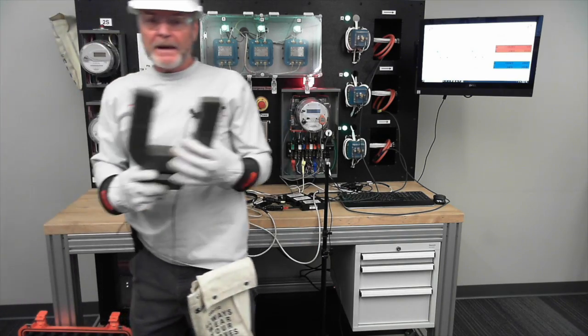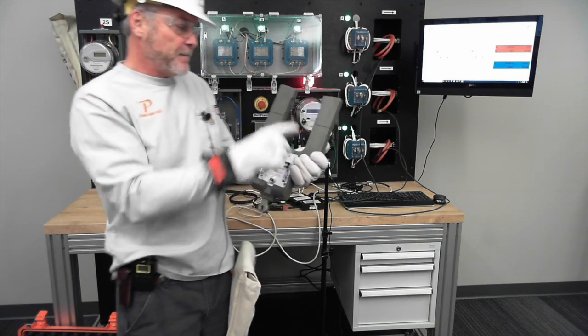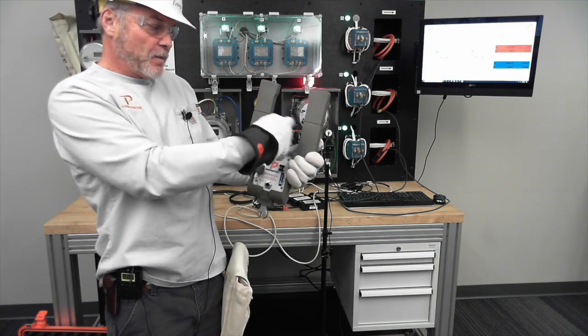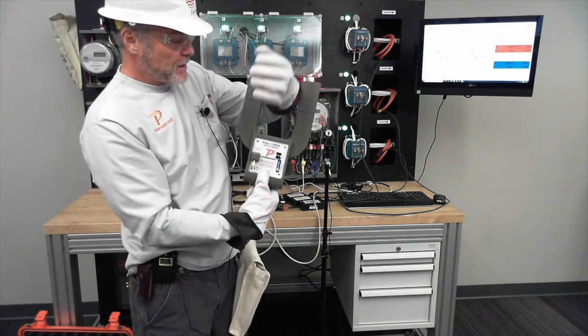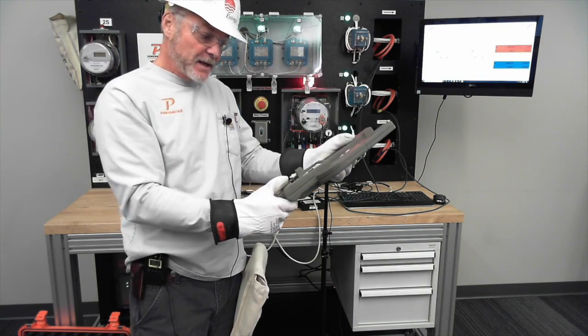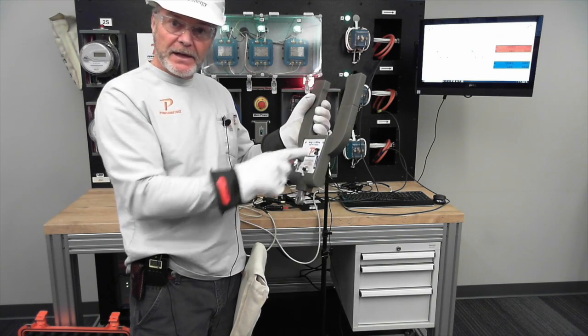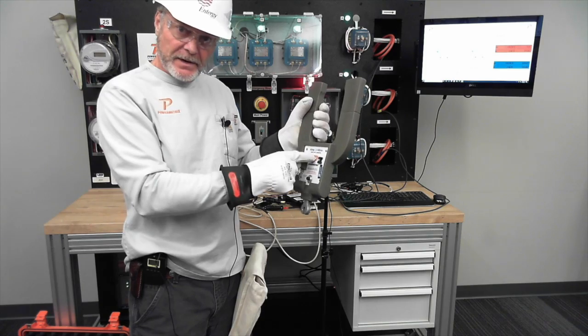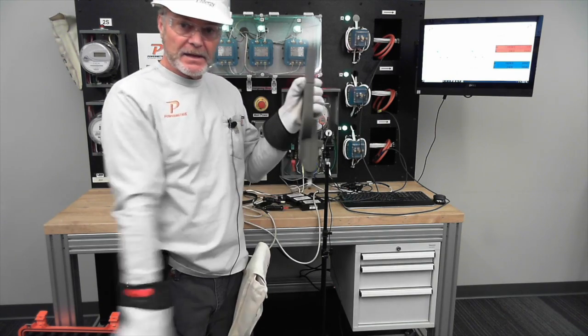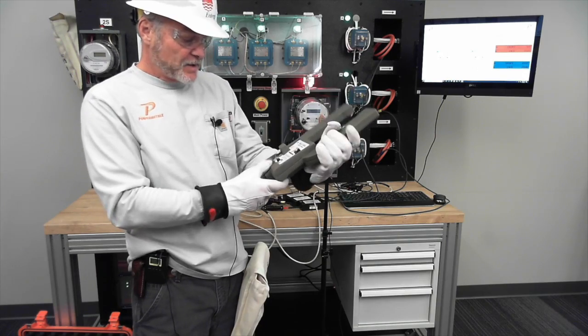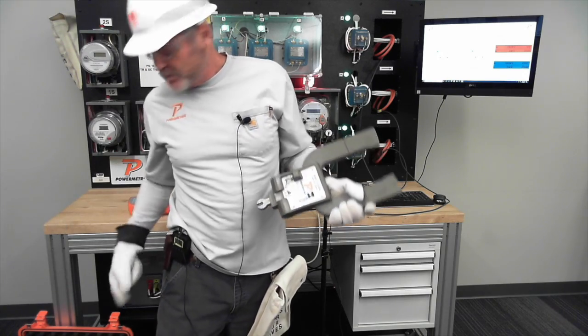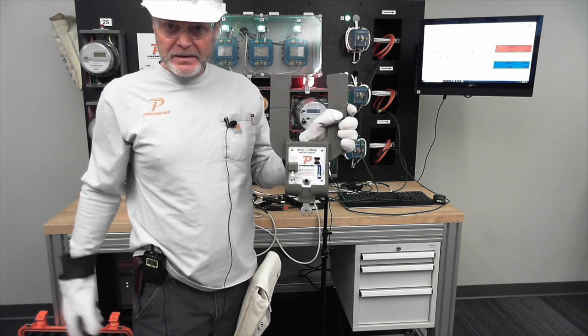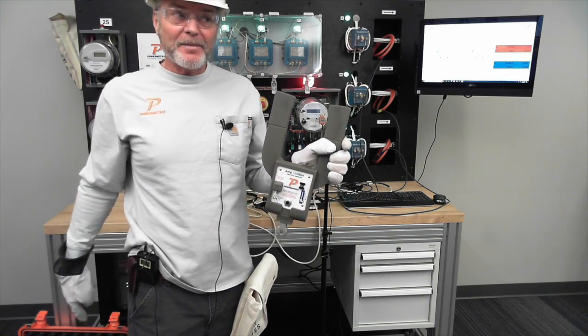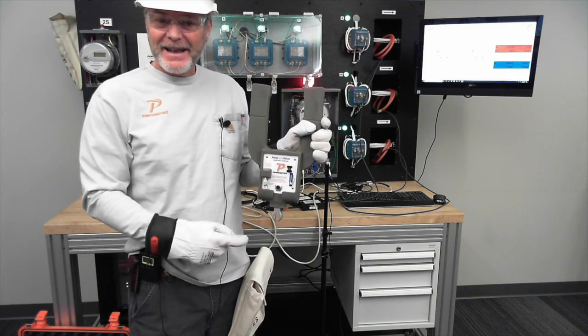So you've seen the HighVolt probe. This goes on the end of the extendo. I want to bottom the conductors out so I'm inside here around my conductors. You always face the label towards the load to get the polarity correct. If you turn it the other way, it'll give you polarity reversal. Make sure when you turn on the buttons you get your green light. You press the button on the receiver or base unit, and also on the head unit. So that's our HighVolt current probe.